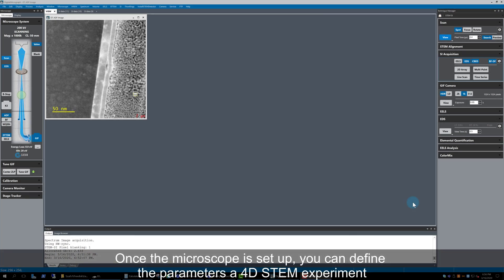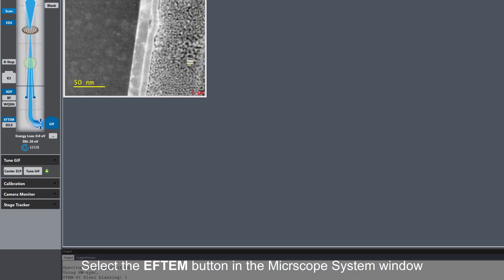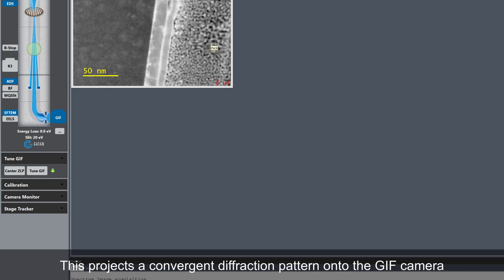As the microscope has already been set up for the EELS and EDS spectrum image acquisition, it is very straightforward to also acquire 4D STEM data. All that is required is to change the filter from EELS mode back to EFTEM by clicking on the EFTEM button in the microscope UI, and a convergent diffraction pattern is projected onto the GIF camera instead of an EELS spectrum.